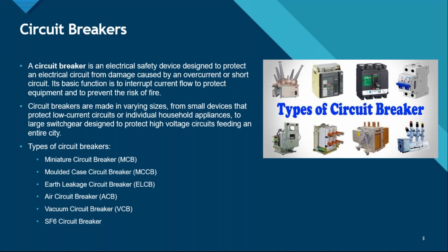also SF6 circuit breakers. Particularly with SF6 circuit breakers, when they are connected to the transformer, in case you want to break the circuit manually, there can be high chances of arcs getting developed between the contacts of a circuit breaker. SF6 circuit breaker is out in the open, so whenever breaking a circuit, no one should be around that circuit breaker. When it comes to ACB or VCB, also there can be high chances of arcs getting developed. But for ACB and VCB, we have air in between, or vacuum in between, to contain the arc from spreading and starting an arc flash or an arc blast or a fire or an explosion. Right. So then we have air circuit breaker, that is the ACB, vacuum circuit breaker, and SF6 circuit breaker.